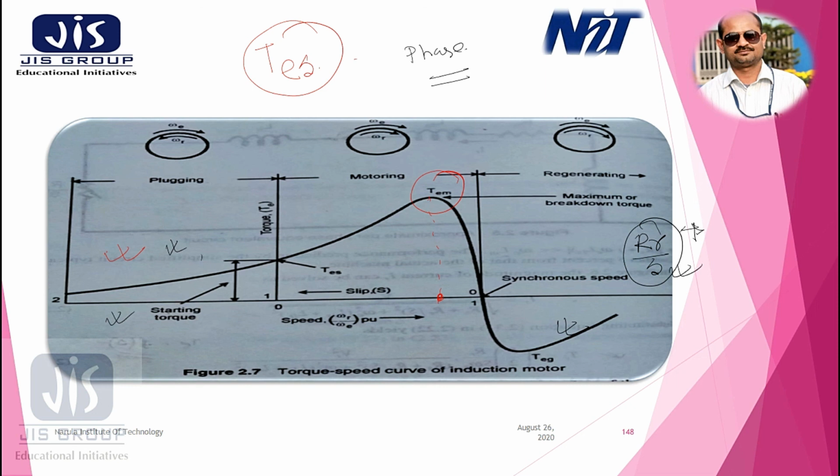So with a variable frequency power supply, the machine stator frequency can be controlled to be lower than the rotor speed to obtain a regeneration braking effect. So an induction machine can continuously operate as a generator, that is an induction generator, if its shaft is rotated at super synchronous speed by a prime mover such as a wind turbine. So using a wind turbine, you can continuously rotate the induction motor rotor at super synchronous speed, that is, a speed higher than the synchronous speed ns. So it will become the induction generator.